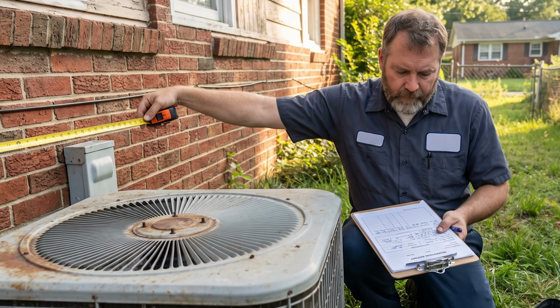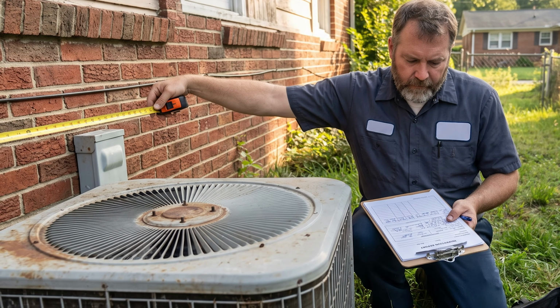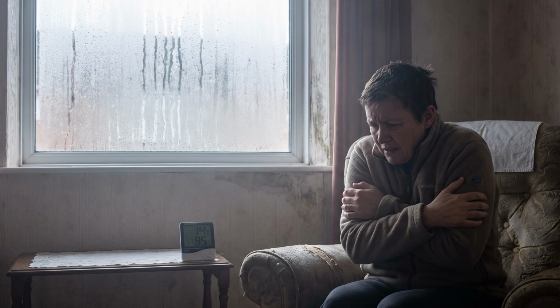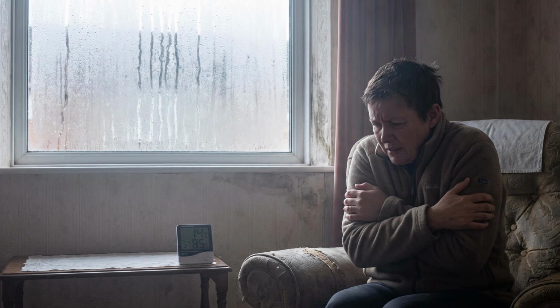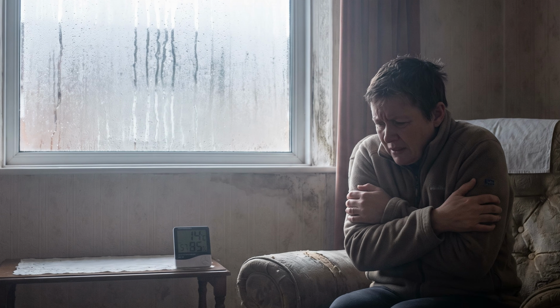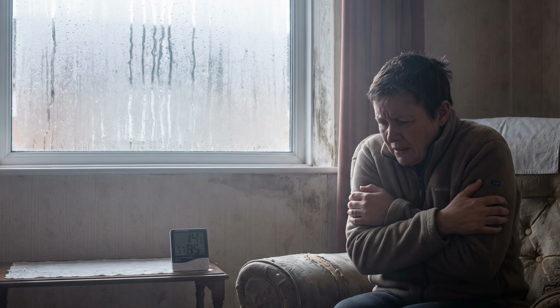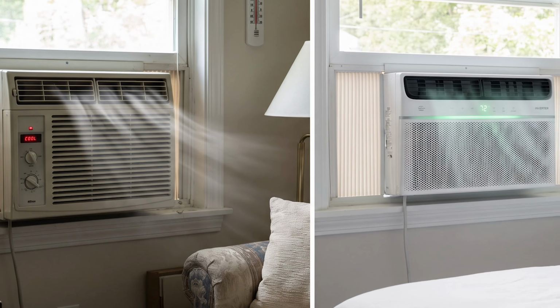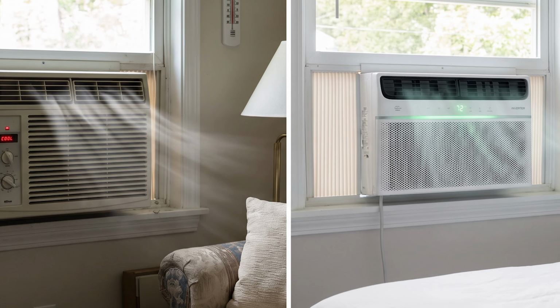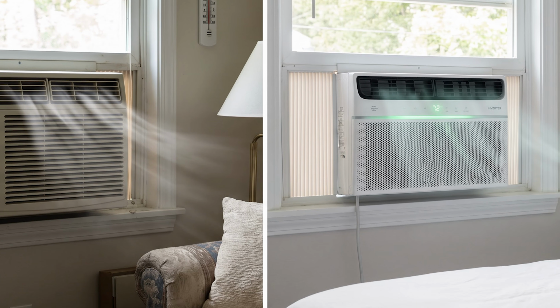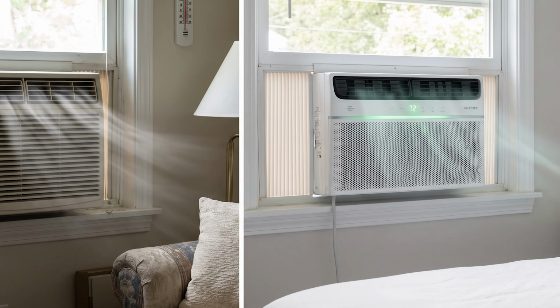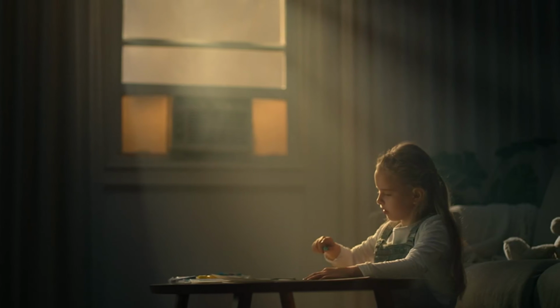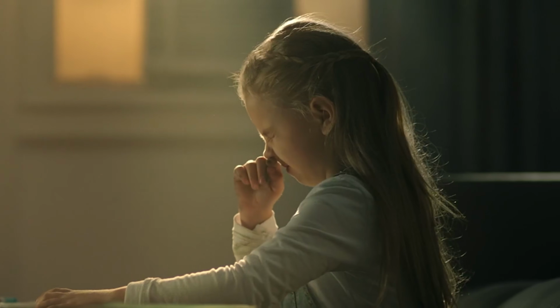When you buy an oversized unit, it is too powerful for your house. It blasts the rooms with cold air and hits the target temperature in just 5 minutes. Then it shuts off. This is called short cycling. Because it only ran for 5 minutes, it never had time to pull the humidity out of the air. The result is a house that feels like a cold swamp. It's 70 degrees, but your skin feels clammy. The air feels heavy. This high indoor humidity eventually leads to mold growing inside your walls and air ducts.